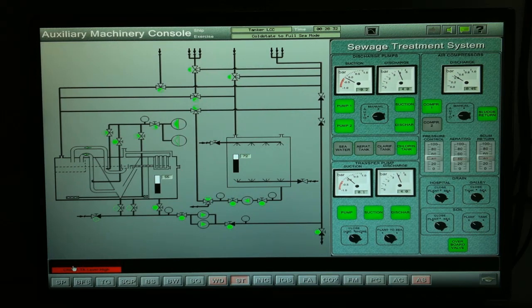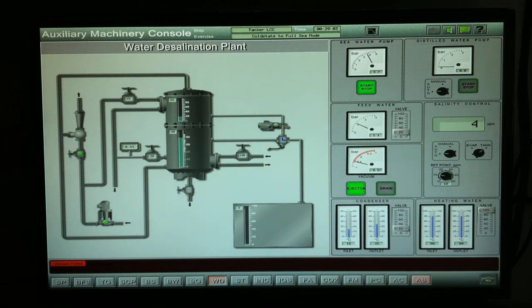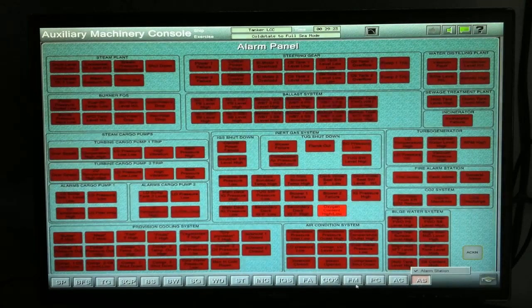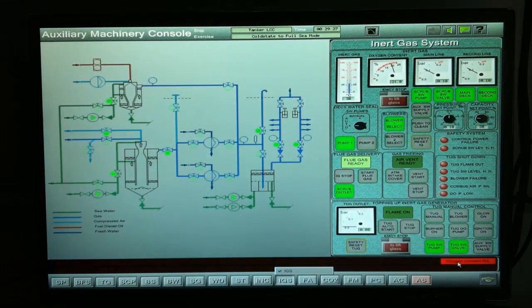So no more alarm on the sewage holding tank. Just need to wait. Okay, so no more alarm on the chlorination tank. So once you don't have the alarm on the chlorination tank, anyway, automatically the pump will stop. Okay, so we'll still have to monitor this one. To check on the vacuum here. Vacuum of the water desalination plant. Okay, so no more problem with the vacuum. That means everything is in normal condition, except for the inert gas oxygen content.